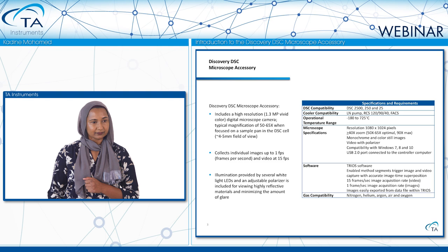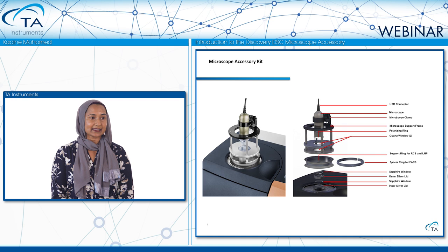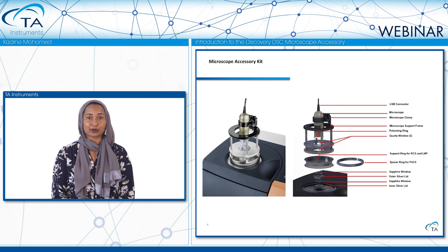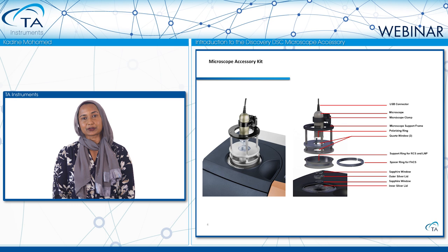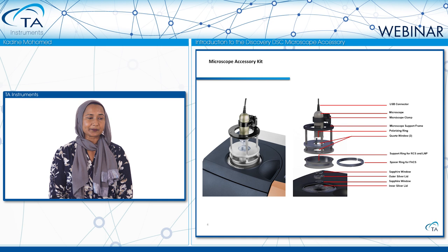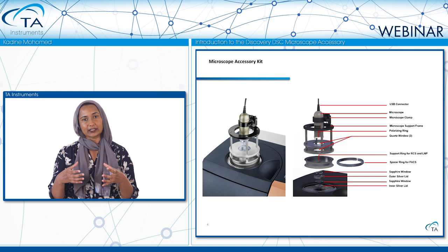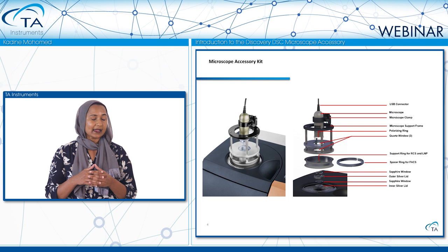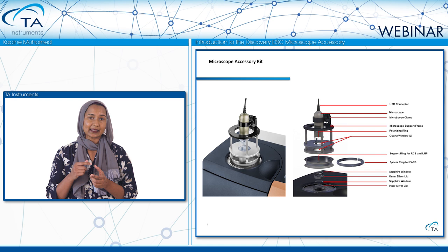Let's look at the components of the accessory kit. We have the microscope camera connected to the support frame, and the camera is connected to the computer controlling the instrument through USB. Looking down the frame of the accessory, we have quartz windows, a support ring for the RCS and liquid nitrogen pump, and a spacer ring for the FACS — which allows the full temperature range of 725 degrees. There are also cutouts within the support ring and the inner and outer silver lids to allow viewing directly above your sample.